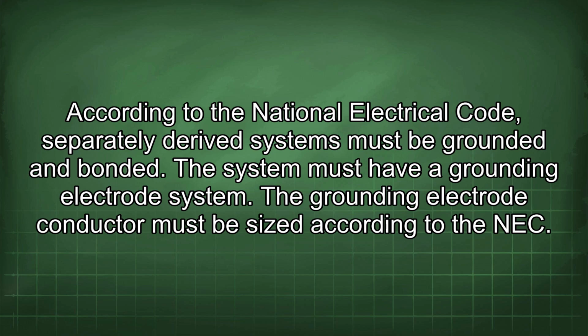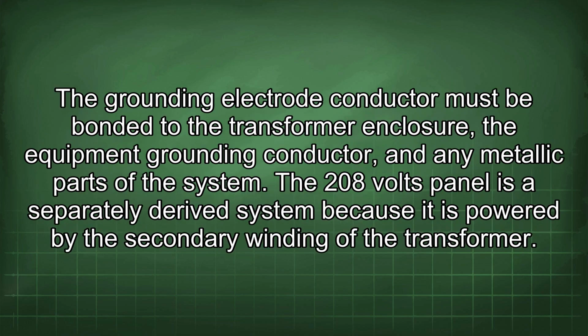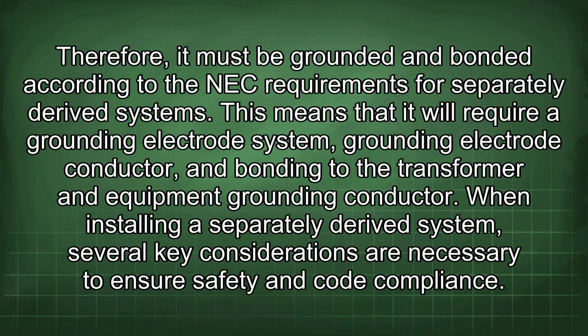The system must have a grounding electrode system. The grounding electrode conductor must be sized according to the NEC. The grounding electrode conductor must be bonded to the transformer enclosure, the equipment grounding conductor, and any metallic parts of the system. The 208 volts panel is a separately derived system because it is powered by the secondary winding of the transformer. Therefore, it must be grounded and bonded according to the NEC requirements for separately derived systems.